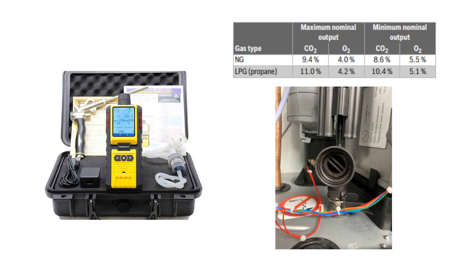Next, check the gas air ratio using your combustion analyzer and correct if out of range. Follow the chart shown for natural gas and propane.